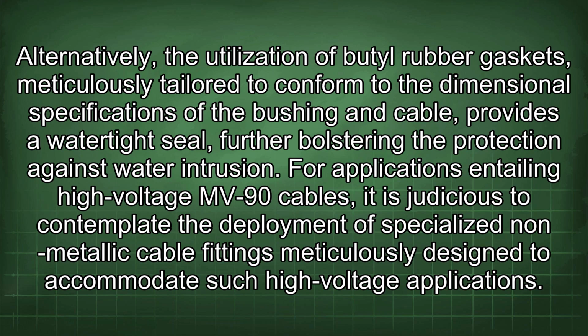Alternatively, the utilization of butyl rubber gaskets, meticulously tailored to conform to the dimensional specifications of the bushing and cable, provides a watertight seal, further bolstering the protection against water intrusion. For applications entailing high-voltage MV-90 cables, it is judicious to contemplate the deployment of specialized non-metallic cable fittings meticulously designed to accommodate such high-voltage application.